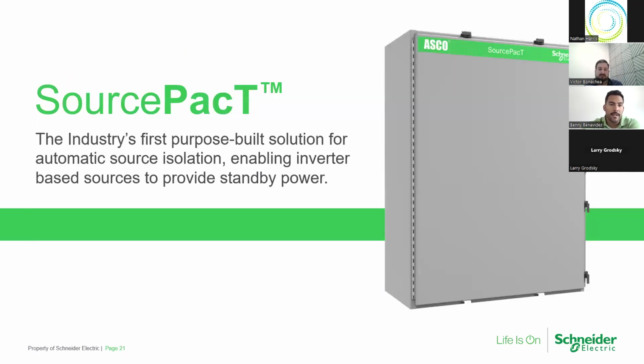And with that, this leads to SourcePacT. A lot of the automatic interconnection switch, the UL 1008 listing, all that is based on our latest product, SourcePacT, and the National Electric Code references it as a microgrid interconnection device. This is the industry's first purpose-built solution for automatic isolation and reconnection to utility to enable inverter-based sources to provide standby power. We talk about lithium-ion chemistries, but there are different types of energy storage systems out there that people want to utilize.